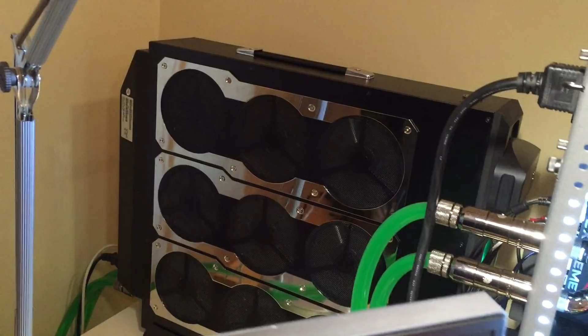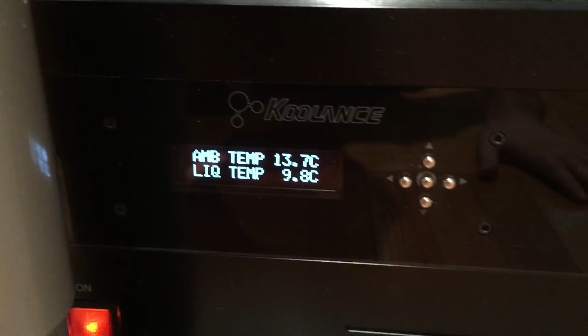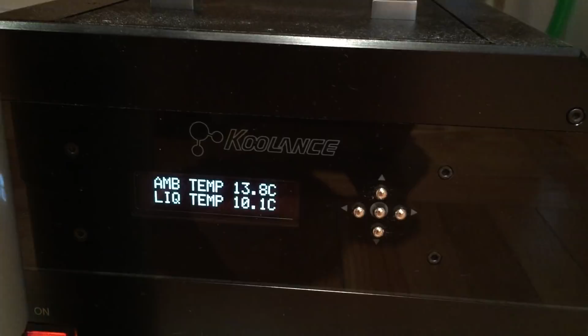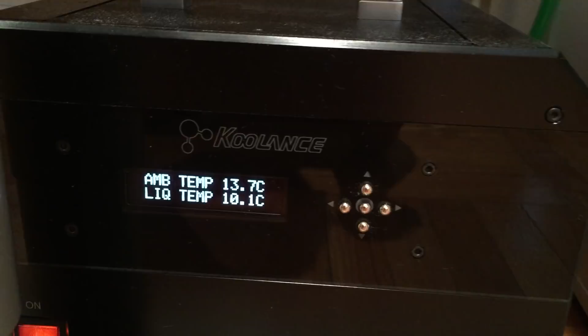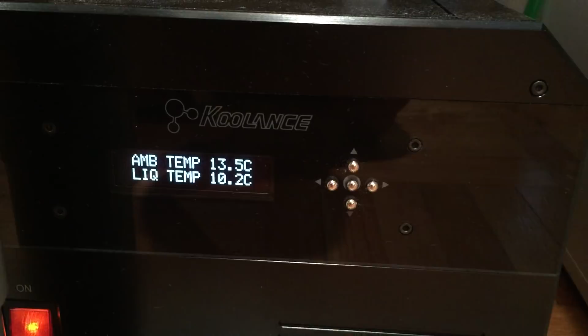Alright, let's take a look at the chiller, it's just standing right here. Let's see what the configurations are set to. At the moment, liquid temperature is set to 10 Celsius. This is something you want to probably keep around 10 to 18, depending on your ambient temperature, in order to avoid condensation. If you go below 10, this probably will result in condensation on your tubes, and it will drip, and those drops will leak right onto your components.